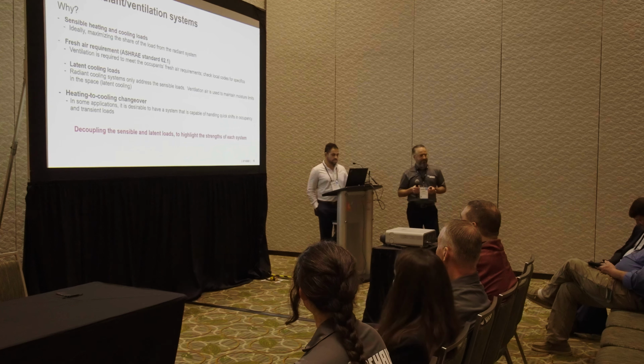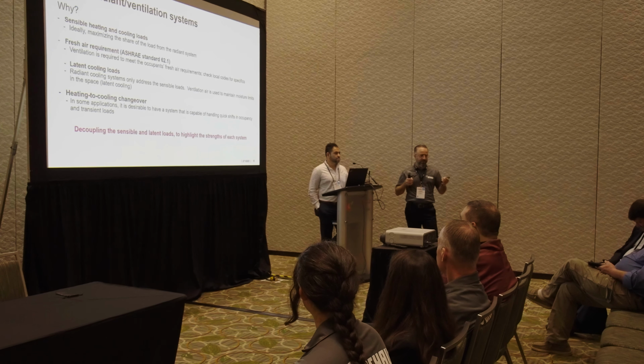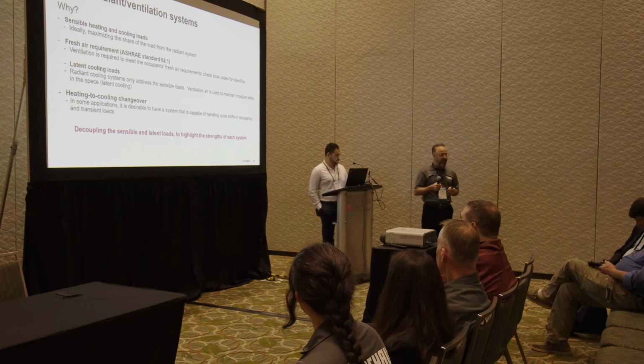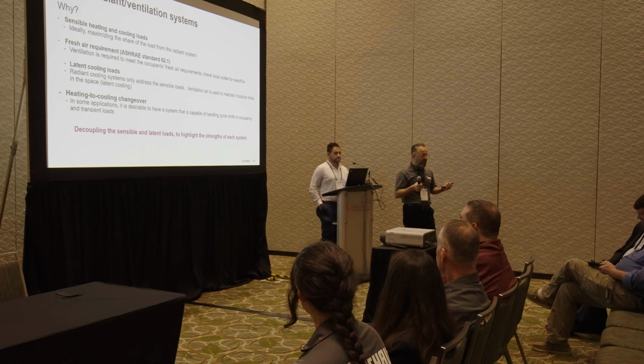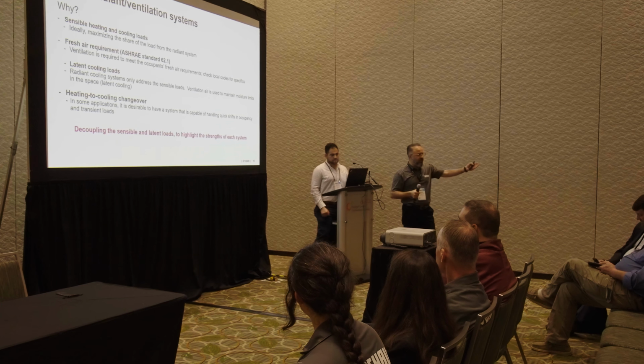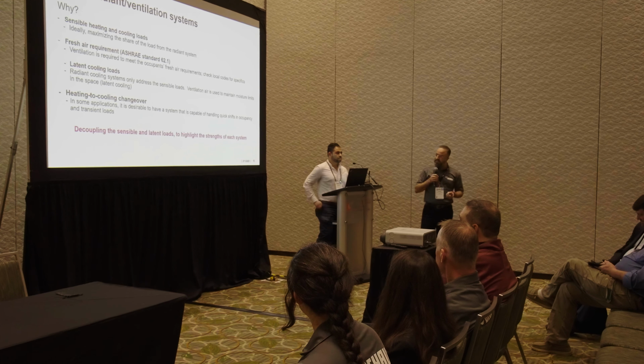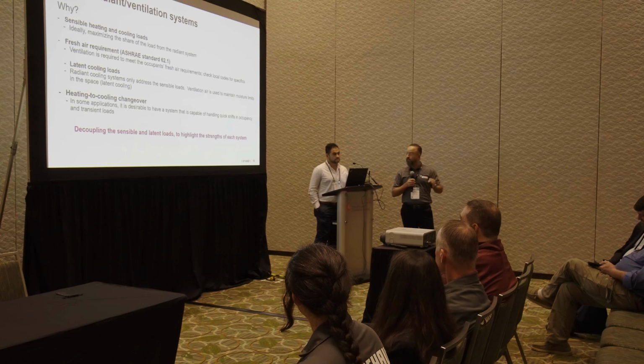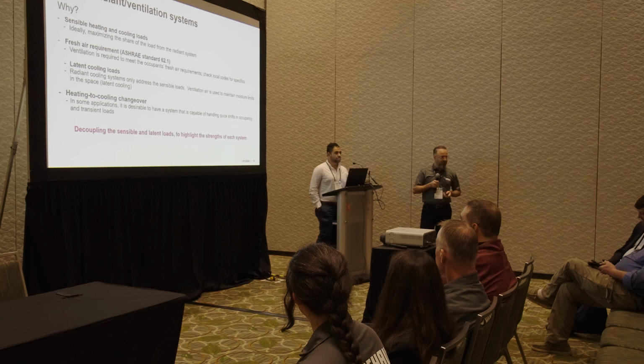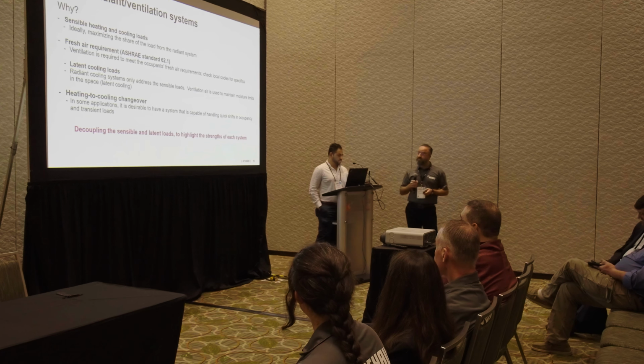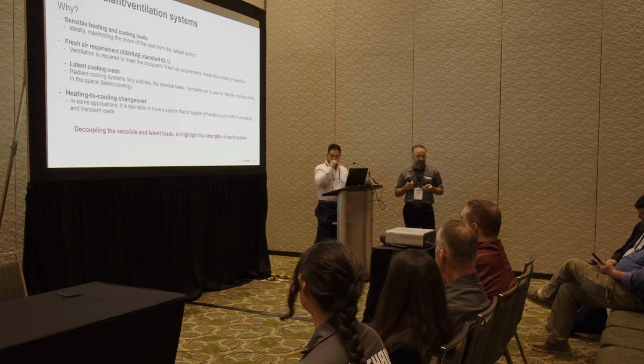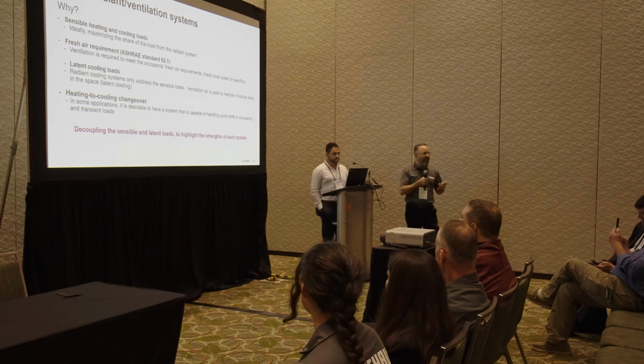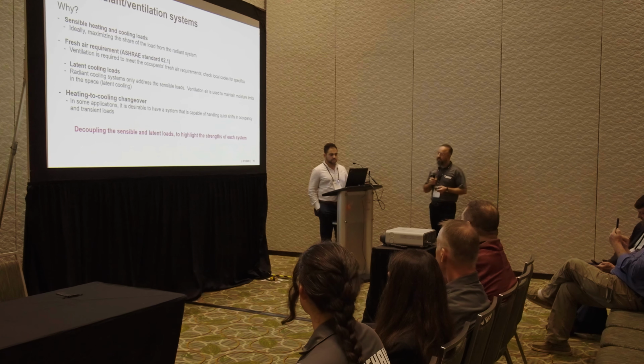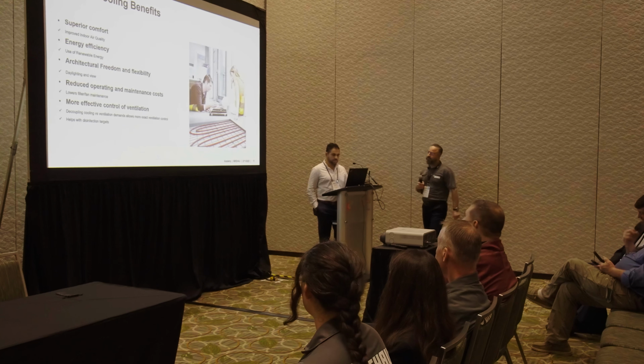Let's say in a shoulder season, in an area where you may feel a little bit cold in the morning, but around noontime it gets warmer. Or let's say in this room, all of a sudden I have 50 folks coming in. A radiant system is a slow response system. So for those times when you have a quick shift in occupancy, you need an air system to back up your radiant application. So these are the three main reasons that you always see radiant cooling applications in a hybrid mode. So you will need an air system to go with it.